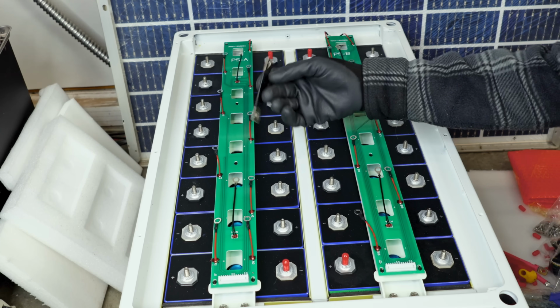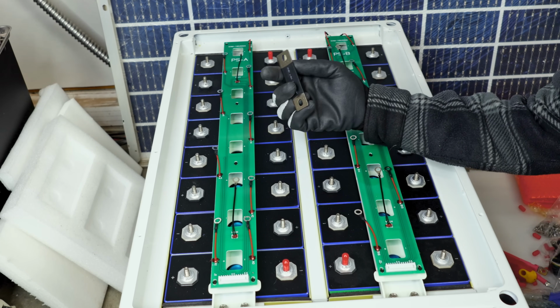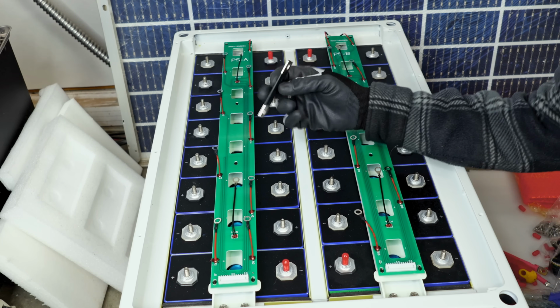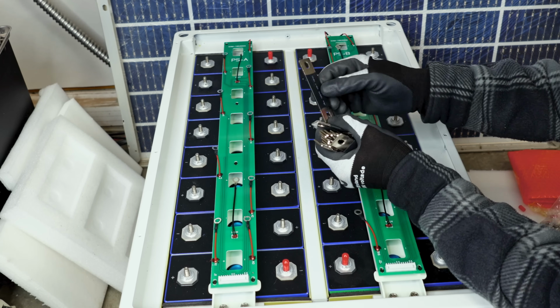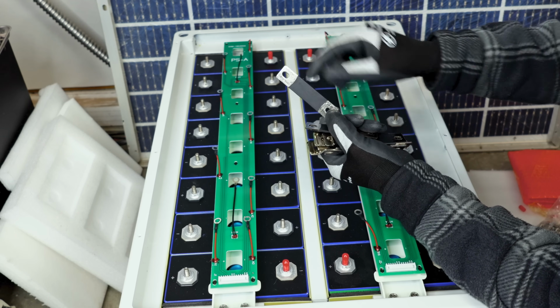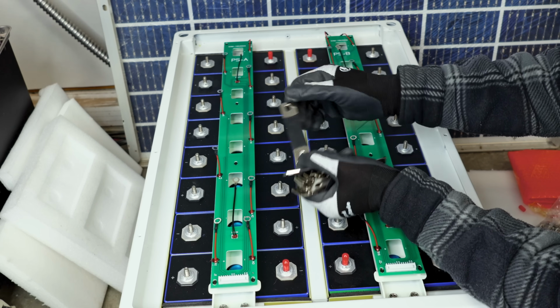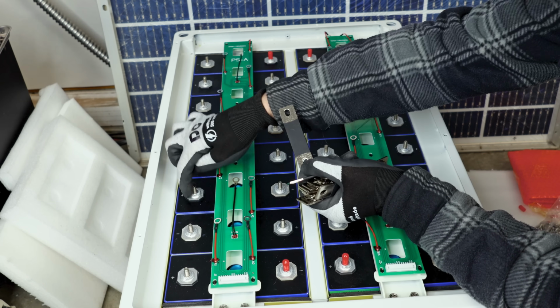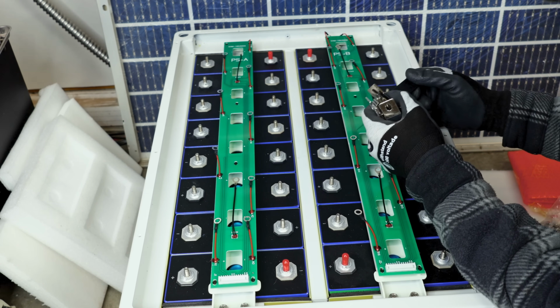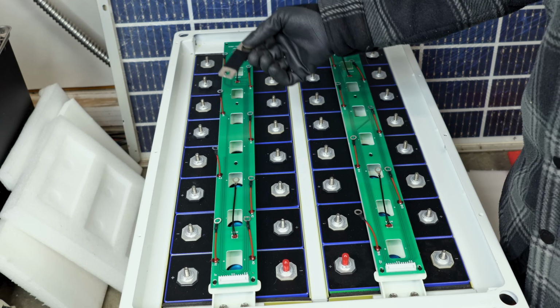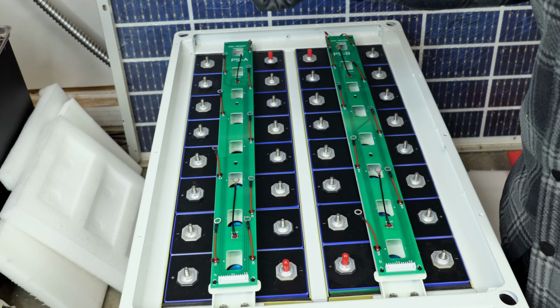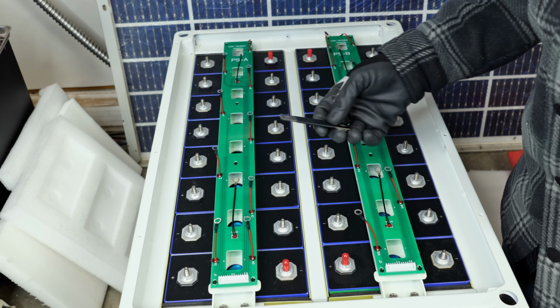These are the bus bars that come with this build. It's just a solid copper bus bar, not flexible in the middle. My preference is to have bus bars with a flexible middle, so that when there's expansion and contraction it doesn't put stress on the bolted joint. That said, they are slotted, so it'll be okay, just not my favorite. You can always order flexible ones if you want to make an adjustment to your build.